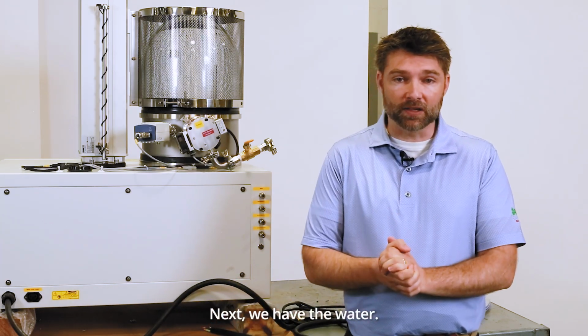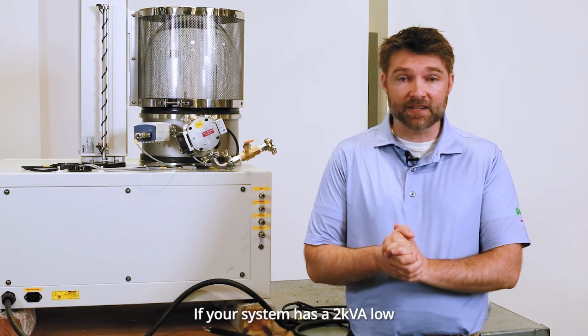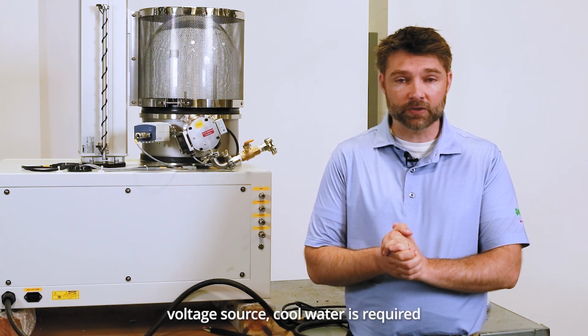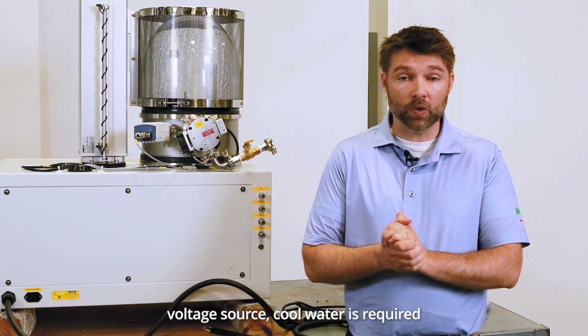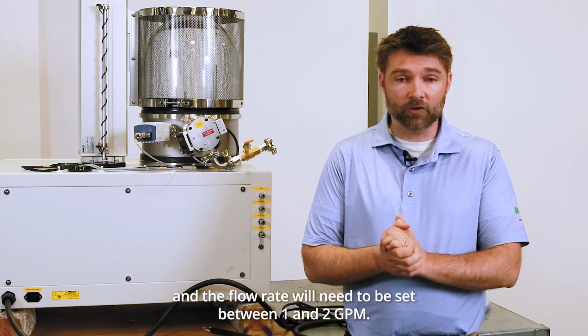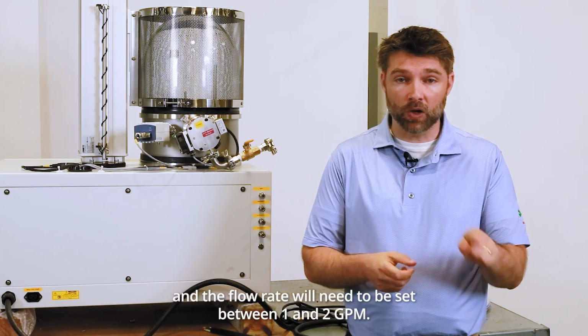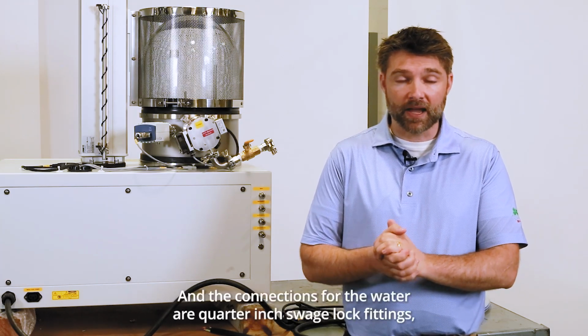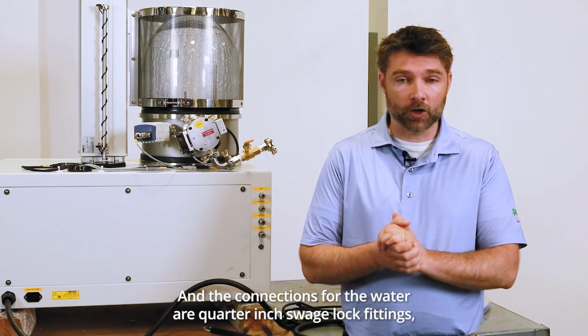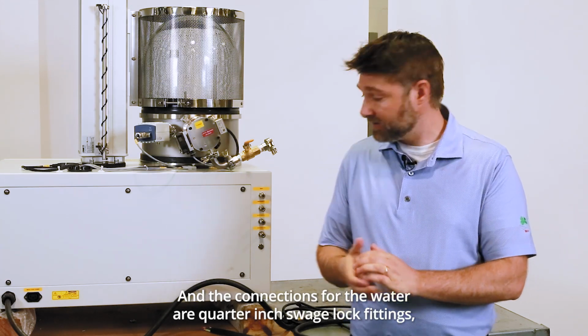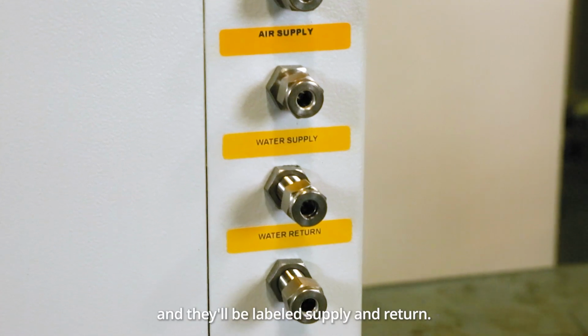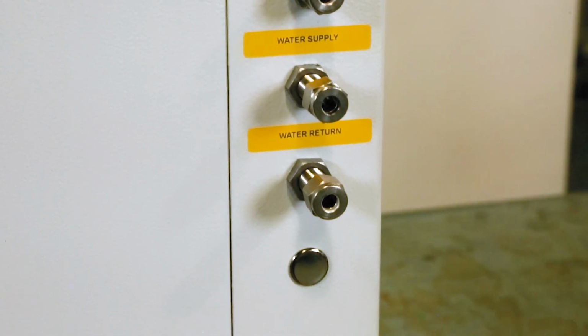Next, we have the water. If your system has a 2 kVA low voltage source, cooled water is required, and the flow rate will need to be set between 1 and 2 GPM. And the connections for the water are 1/4-inch Swagelok fittings, and they'll be labeled supply and return.